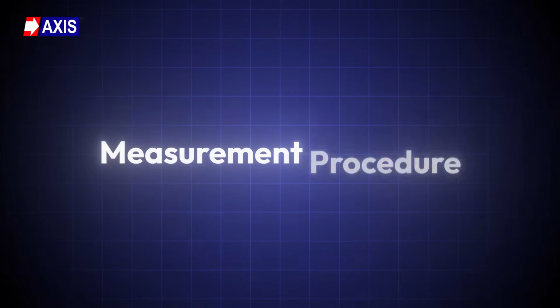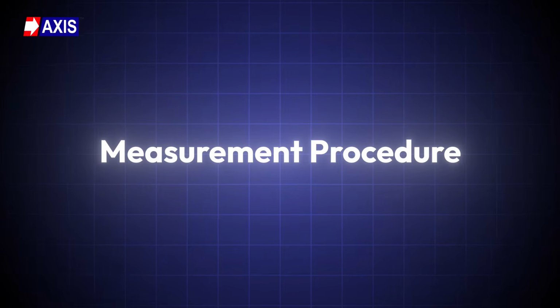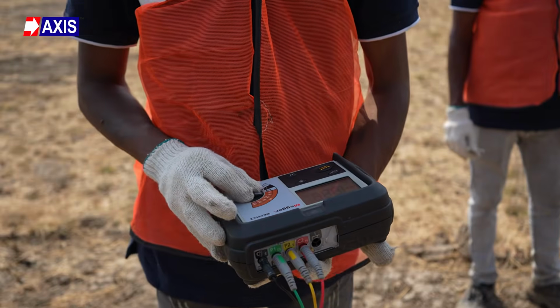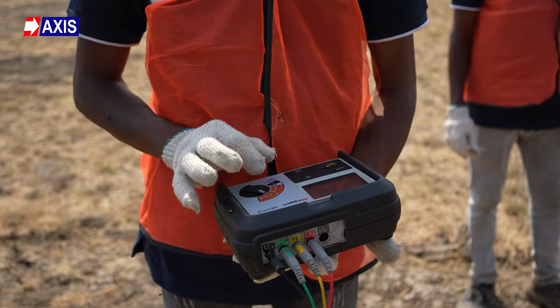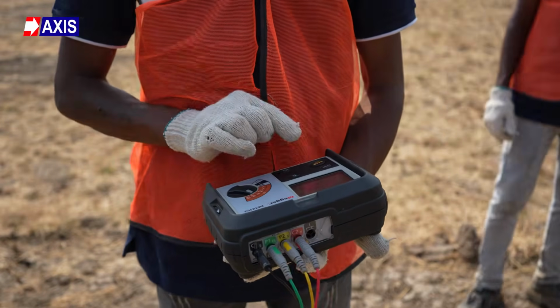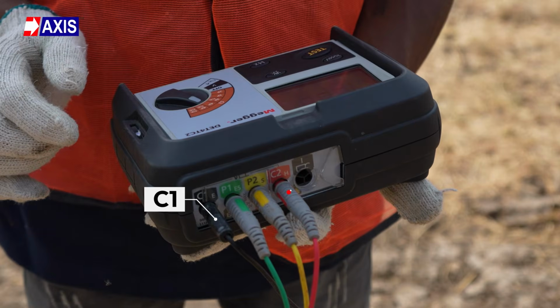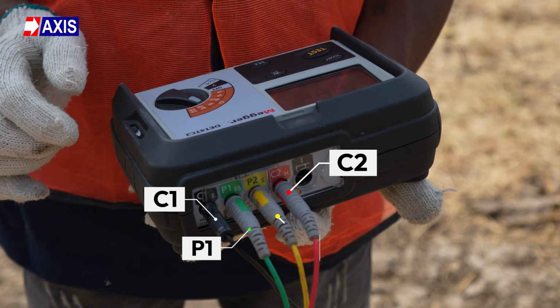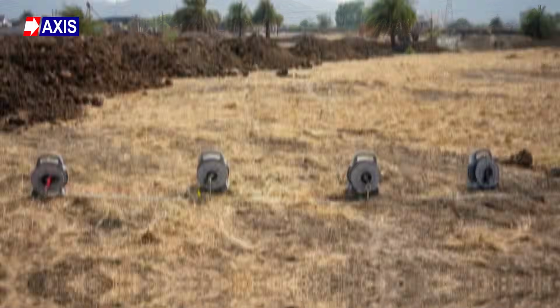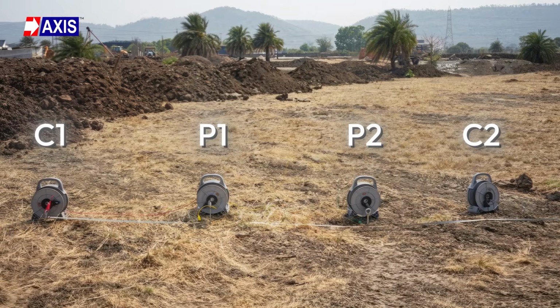Now, let's start with the measurement procedure. You will need 4 auxiliary electrodes for this test. The 2 outer electrodes carry the current. Call them C1 and C2. The 2 inner electrodes measure the voltage. Call them P1 and P2. All 4 are temporary test spikes driven into the ground.